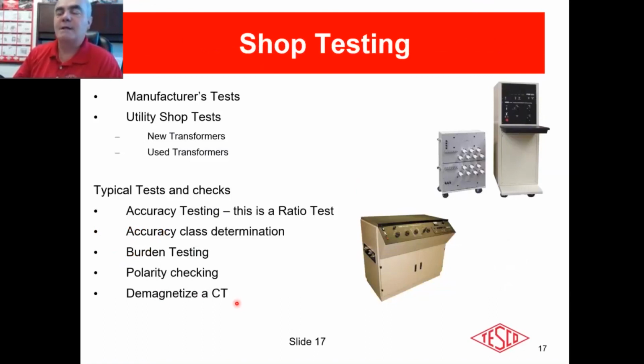And then demagnetizing the CT. You want to demagnetize your CT anytime you do any work in the field and before you put it out in the field. Well, you would wonder, why do I need to do that before I put it out in the field? You want to do that because CTs can come from the manufacturer magnetized. If you're not checking them, if you're not doing a 100% check, you can put that magnetized CT out in the field and you may not know it until the first time you do a field check on it, which may or may not be 90 days after, or maybe it's a couple of years after, or if it's a small enough service, maybe you never do it.